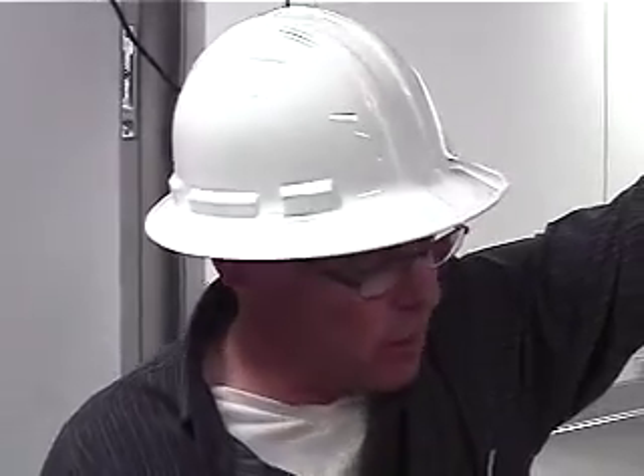We don't take anything out. We don't start taking fans and heaters and all that stuff out. There's just no good way to, because if you did that, you'd have to reset the ring back, because it's not going to get cold on its own. So we leave it to set itself back up, because usually what happens in a high temperature alarm is a power issue or something. Once that's restored, it's restored. You don't have to acknowledge any alarms. You don't have to do anything. It'll reset itself regardless of what the issue is. Okay, you might have to fix something, but there's no resetting or acknowledging like some systems will do.